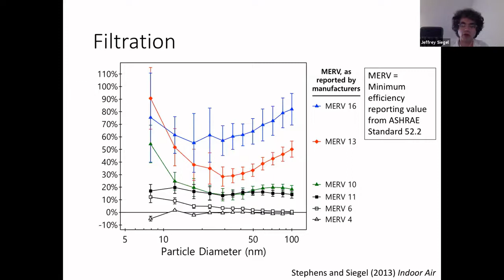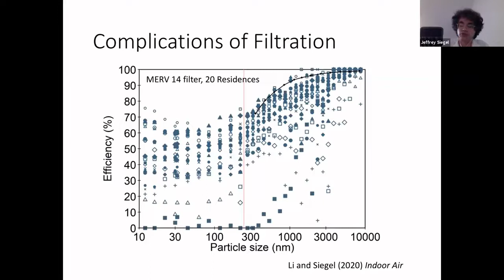Now, the problem even with having a MERV is that a MERV is a fixed quantity. The actual performance the filter gets is a function of the building and how the filter is installed, as well as the filter itself. As one demonstration of this, this is the exact same MERV 14, a relatively high performing filter, installed in 20 different homes in Toronto. You can see that its measured installed efficiency ranges from close to 0 for a lot of particle sizes to above 70%. So the filter isn't the only thing that matters—how it's used matters too. And that really complicates being able to make a specific MERV recommendation.